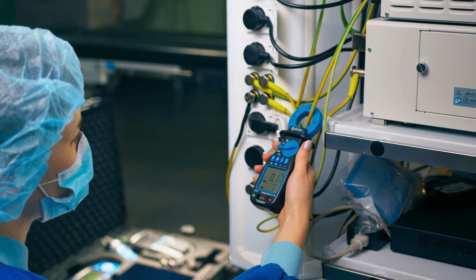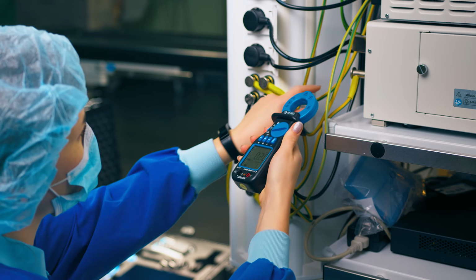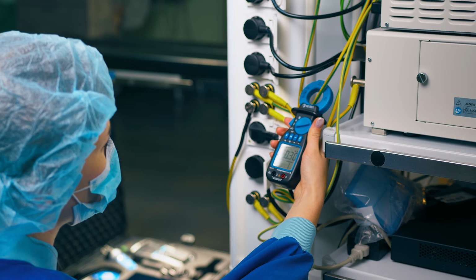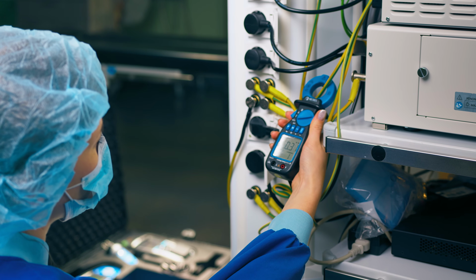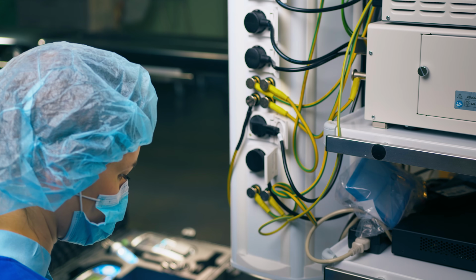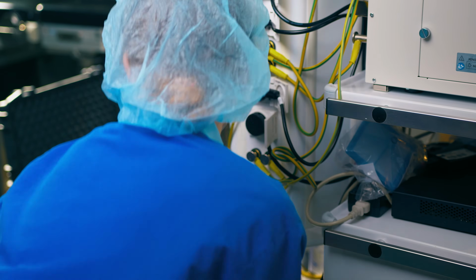All that is needed is to set the MD9273 to measure leakage current, clamp it around the protective earth cables of devices in operation, and check if the results are within acceptable limits.